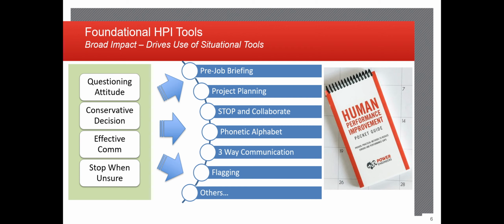Phonetic alphabet. This is something that's used especially when you're doing your isolating. A lot of the relay test switches out in the field are usually labeled with the letters A, B, C, etc., etc. This is to make it easier to understand which switch you're specifically looking at or hoping to open or close. Utilizing the phonetic alphabet reduces the risk of someone mishearing a letter per se, and making sure that everyone is on the same page with what's going to be happening.